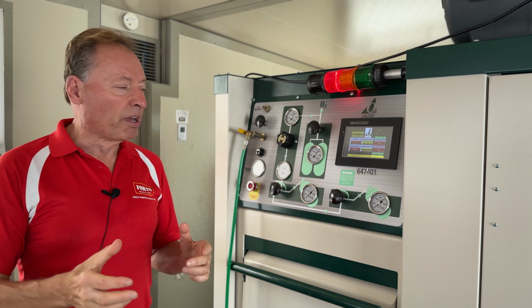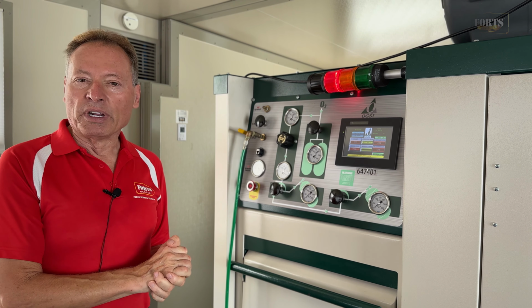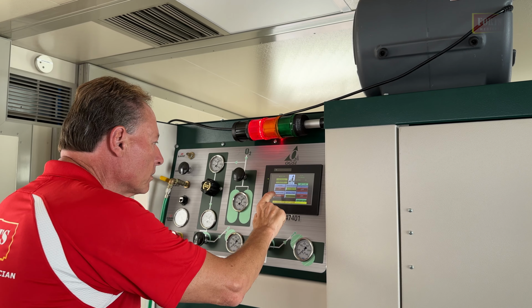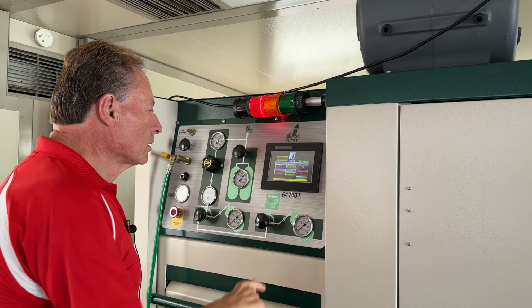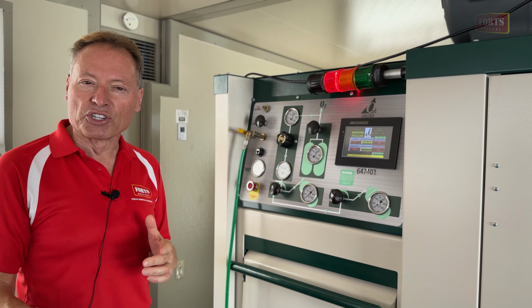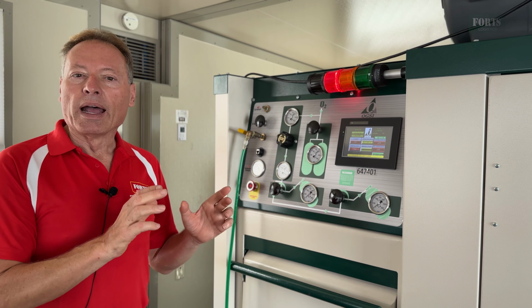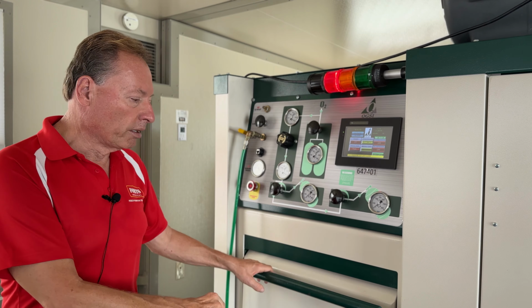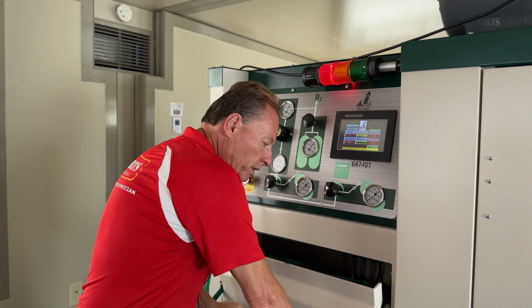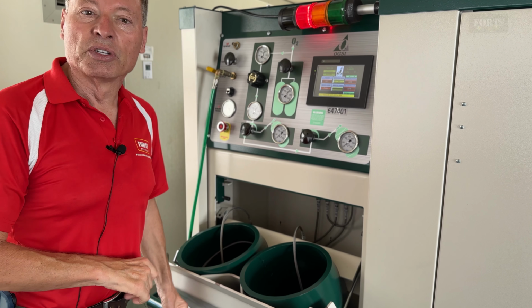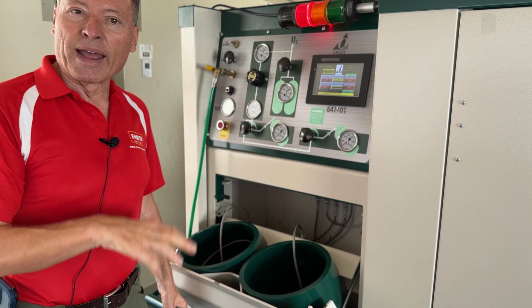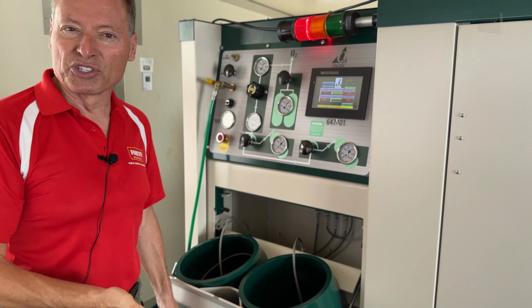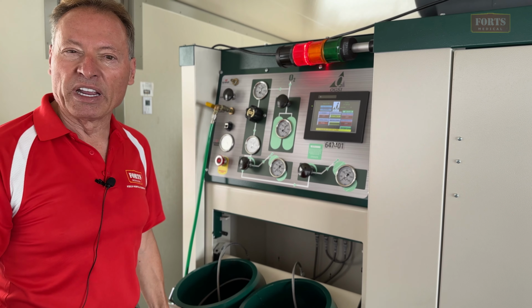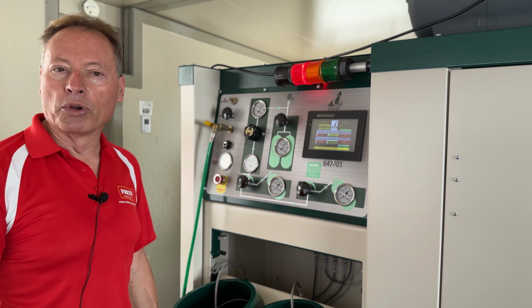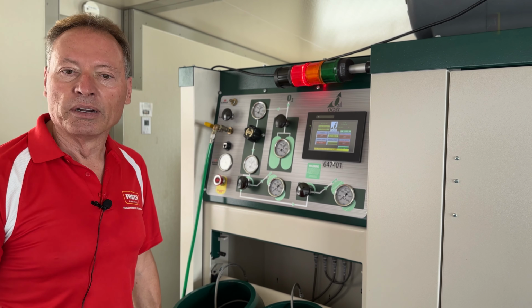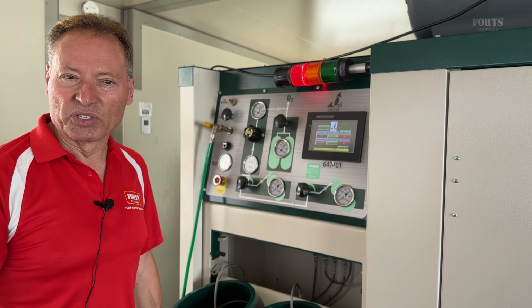We are now in front of our MOGS 100. This unit is quite special. It produces 50 liters per minute of gaseous oxygen at 50 psi, but it can also produce oxygen for storage in bottles at 2200 psi. Over here, we have a special door that allows us to put 2 cylinders to recharge inside. So at this field hospital, we can also fill oxygen cylinders for patients, incoming ambulances, or as we've been doing here for the local population. So the MOGS unit here, quite a special system built into this hospital.